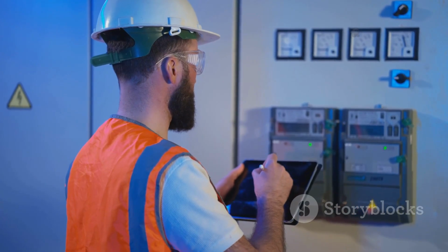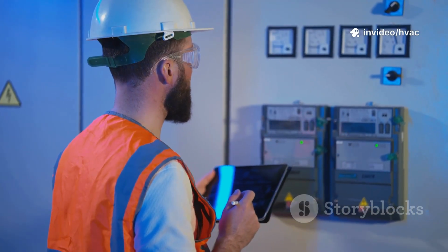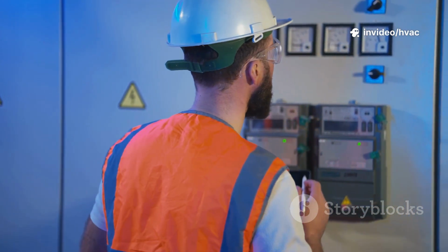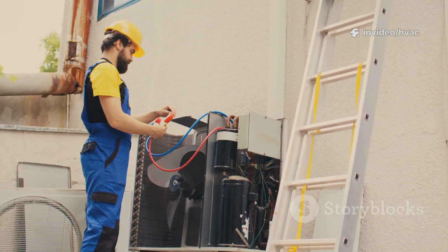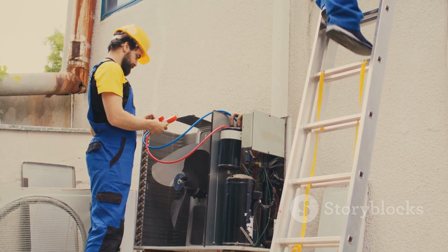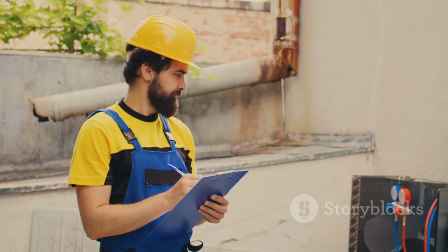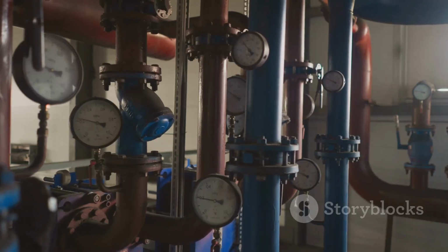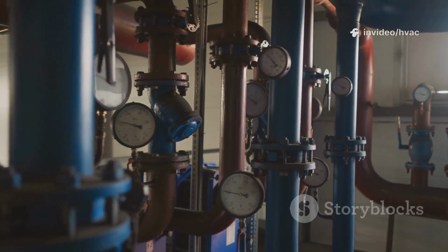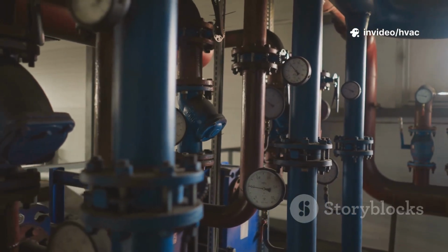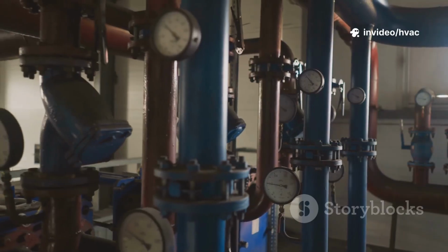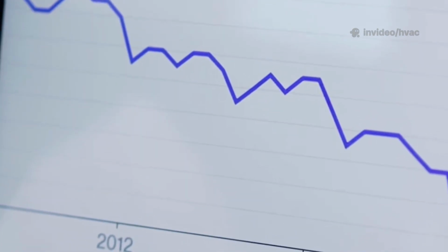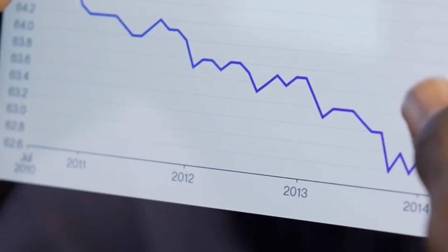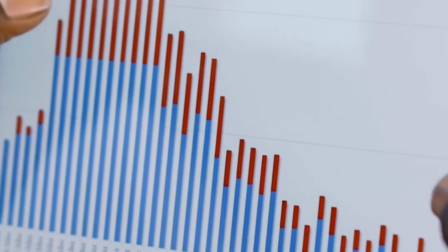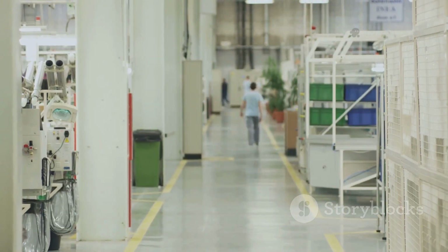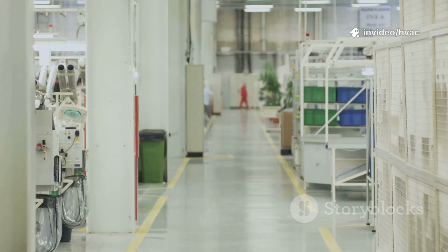From a maintenance perspective, PICVs offer a clear advantage by reducing the burden on facility staff. The dynamic balancing feature means that the system rarely needs to be rebalanced after the initial setup. This saves countless hours of labor over the life of the building. Furthermore, by ensuring the system operates under stable conditions, PICVs reduce wear and tear on expensive equipment like pumps, chillers, and actuators. Fewer equipment breakdowns and less need for troubleshooting mean lower maintenance budgets and a more reliable HVAC system. The system simply works better and requires less intervention from the maintenance team.